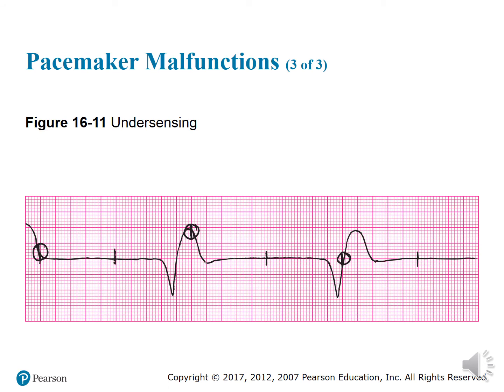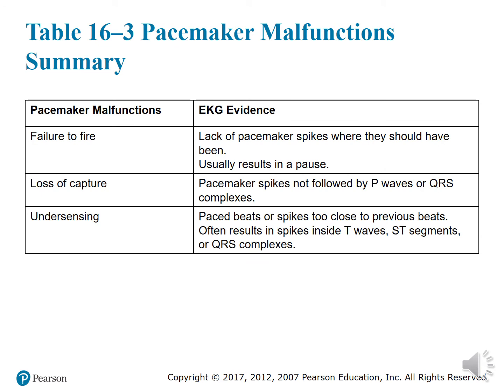All right, this is what undersensing looks like. You see here, what's noted in this is that spike in the QRS complex. You see how the pacemaker is firing at the top of the complex, top of the complex here. Not sure what this is over here, but it's firing in the wrong location right here. It's just not picking up what it needs to because it's going off entirely too fast. All right. So those are the most common malfunctions for a pacemaker.